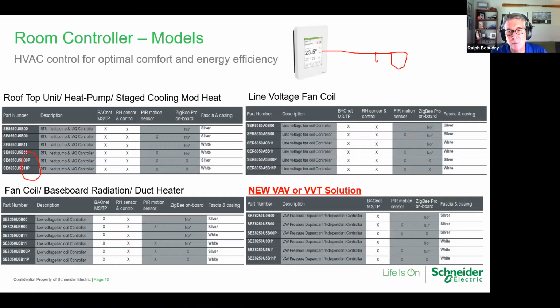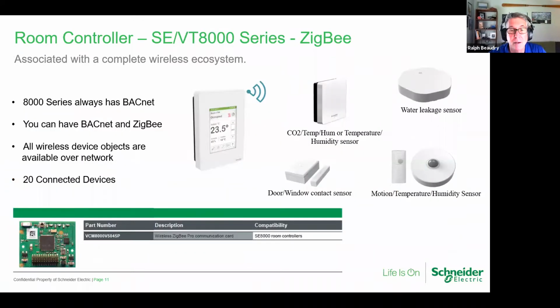And why that's important is when I talk about the Wi-Fi card, I can install a Wi-Fi card and have ZigBee communication both on the same unit. So I can be communicating Wi-Fi back to IP back to my network level controller, and have a bunch of wireless peripherals talking ZigBee. I'll show that here. So again, it always has BACnet MSTP on board. I can have hard connected BACnet MSTP into my 8000. And I also can have ZigBee wireless, which will communicate to an ecosystem of sensors like CO2, temp humidity, or leak detector, or door and window contacts, or motion. It can be one sensor, it can be 20 sensors, it can be 20 of the same kind, or it can be a mix of all of these sensors. Now, if you buy the base model, just the regular BACnet model without the ZigBee communication card on board, you still have the opportunity to buy a plug-in ZigBee card, but it will take up that slot.